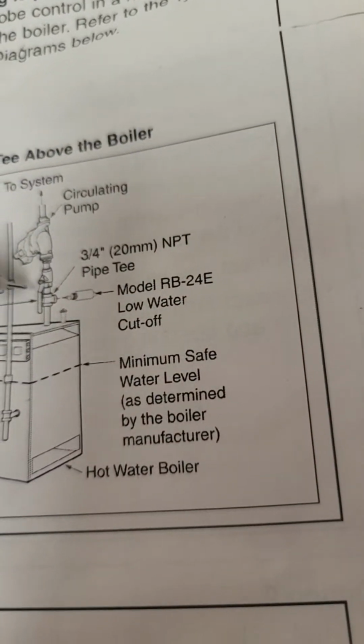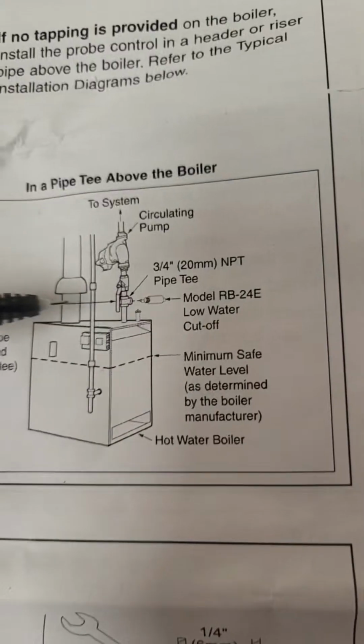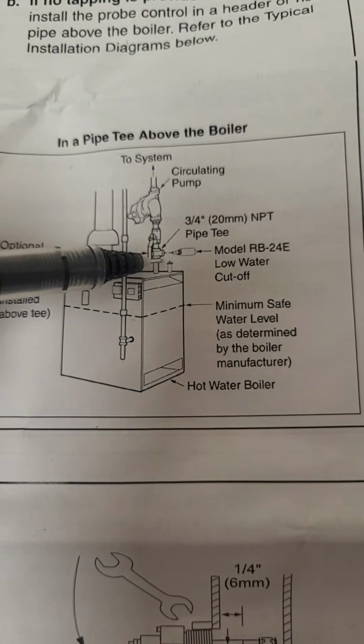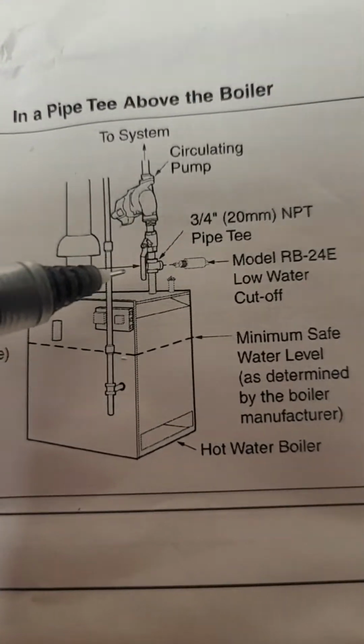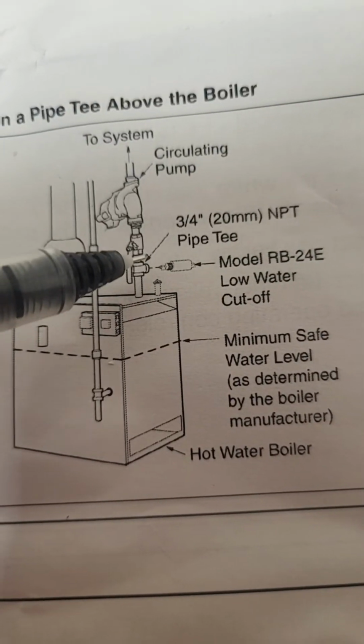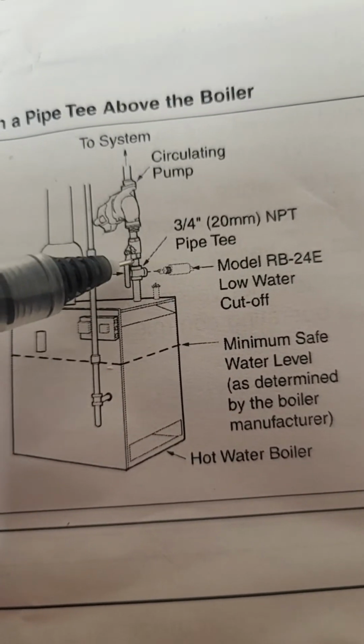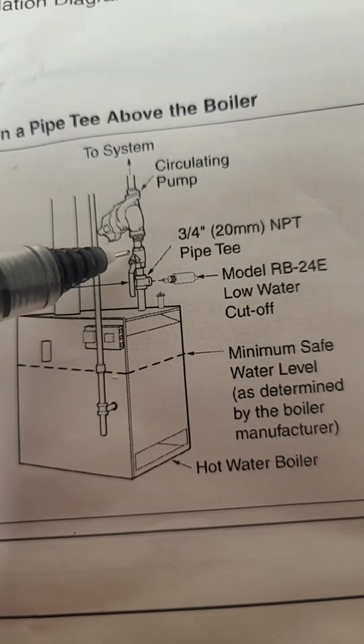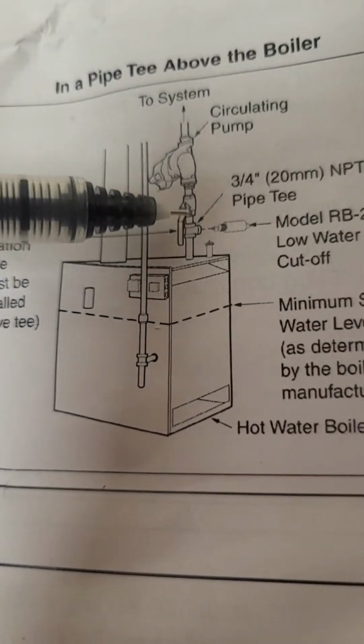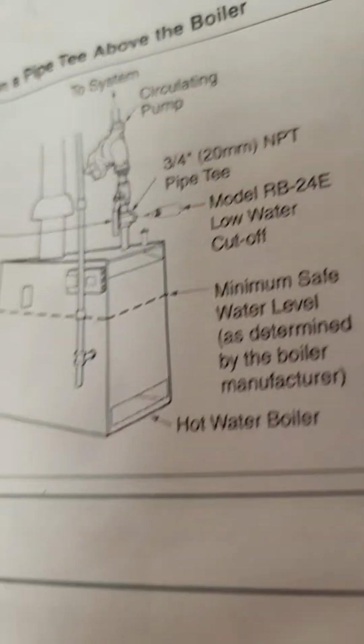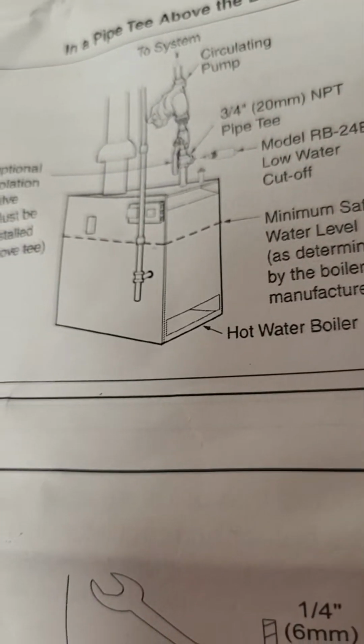Now this particular load, guys, this was an existing low water cutoff that I replaced. It had a T, literally, I just had to unscrew it once I drained the water down out of the boiler. But here's the issue: this boiler didn't have an isolation valve on it. So with no isolation valve, I had to drain everything down, and once I replaced the low water cutoff, I had to refill it and bleed air. That took a whole bunch of time.